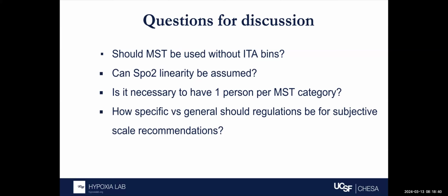Right. If the FDA or ISO wants to ensure that pulse oximeters work across a diverse ethnicity or race, then that has to be a specific thing that is measured, and MST and ITA cannot be used as a surrogate for that. Well, let me cut right to the chase. The standard and the guidance document are on the precipice of being pushed out. So we would like to harmonize these 2 documents, and we want to know what is this common approach that we're talking about. Because right now it says go off and do MST, and it has some categories, you know, 1 through 4, 5 through 7. And I get my letters.